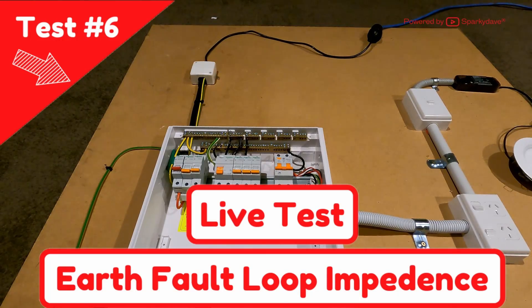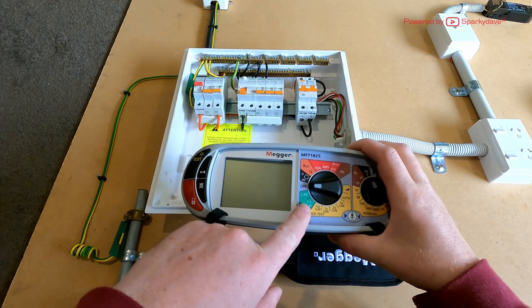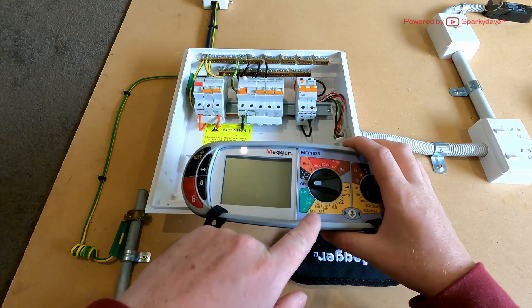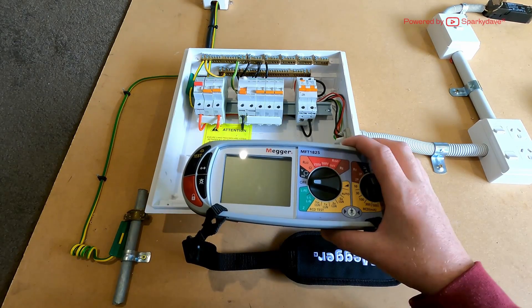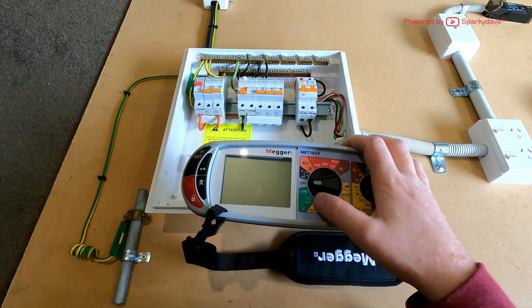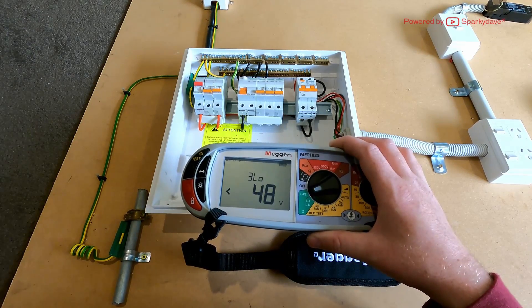Earth fault loop impedance test. Now what we've got here on the Megger is this green area, and we've got our line to earth and line to neutral tests. We do both of these tests because a short circuit can happen between either potential. First of all, we'll throw it on to line to earth.